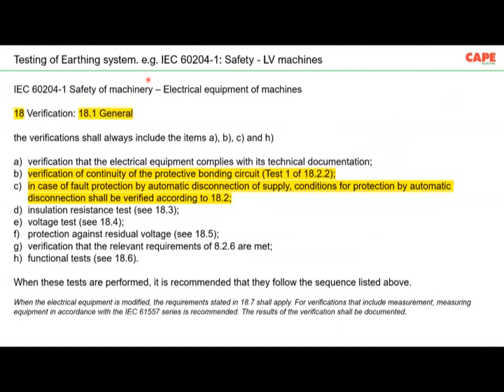Some examples of testing of the earthing system. Especially IEC 60204-1, one of the standards, which is actually on the safety of LV machinery. Clause 18 is the verification. Now you see, the first verification is that the electrical equipment complies with its technical documentation. So the consumer who buys the machine first has to read and understand that it is as per the technical documentation, and then he has to do the testing. The first testing you see here.